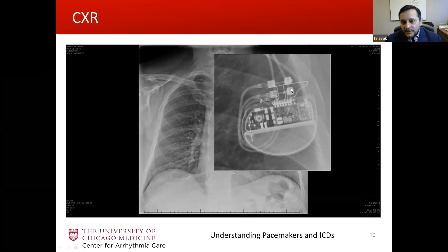There could have been some sort of make or break connection involving this pin header confluence. And of course, at the time of generator exploration, you can see the pin going through in the atrial lead, and this is missing in the ventricular lead. So the teaching point here is that device malfunction is an infrequent cause of syncope after pacemaker implant. Remember that. But you do have to go through this in a steadfast way, to rule in and rule out certain things about pacemaker function.